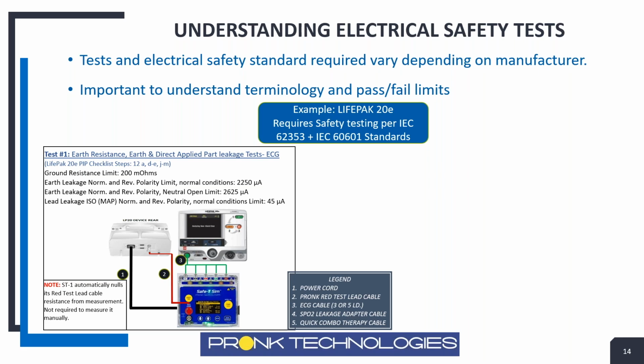And they want you to do an earth leakage test under these conditions, normal and reverse polarity. And so you can see the pass-fail limits are there at 2,250 microamps, which generally speaking, you think that's pretty darn high. But the way this device is designed, it's perfectly acceptable to have basically 2.2 milliamps of current as a leakage pass-fail limit. So if your organization follows NFPA standards, and NFPA standards allow a maximum of 500, well, you're never going to get this LIFEPAK to pass because it could have much higher current leakage than that. And so that's where you have to make sure you're referencing the service manual because they may have the device designed according to a different standard.